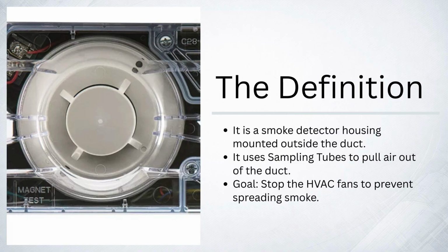A duct detector is essentially a standard smoke detector head inside a special housing mounted on the outside of an air duct. Its job is not to detect a fire in the room. The ceiling detectors do that. The duct detector's job is to sense smoke traveling through the HVAC system itself. When it trips, it performs a specific function called shutdown. It kills power to the HVAC fans and closes dampers to stop the building from pumping toxic smoke into every room.